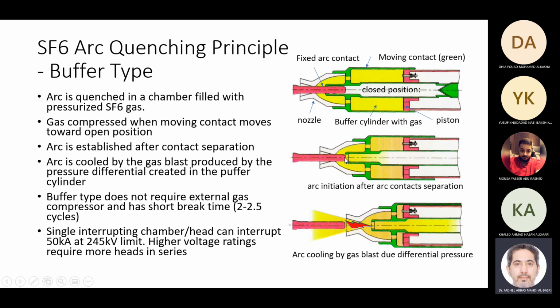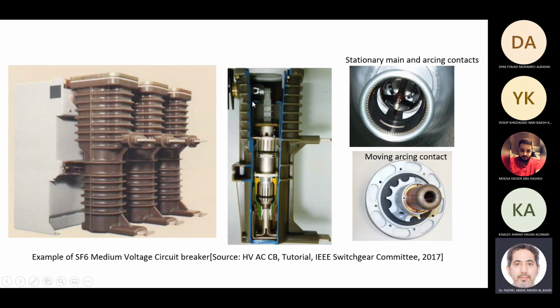Once the fixed contacts separate from the moving contacts, the gas will flow first through this, and then once this has also moved beyond the nozzle, the gas will go through here. That's why we will be able to quench the arc. This is the internal construction of the SF6 breaker. This is the mechanism to open and close the breaker, and this is the SF6 chamber, the interrupter, we call it.